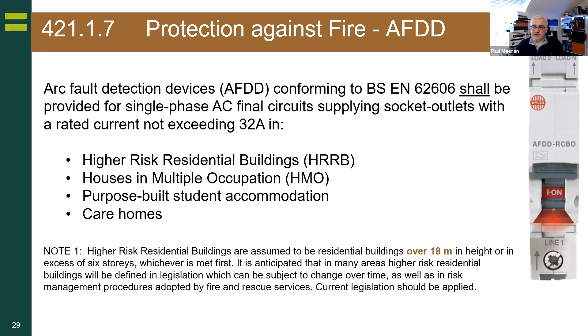For me, I'd use the rule of thumb: anything a plumber can touch. Immersion heaters are high current using technology, and there's a reason behind that which we'll get onto. But for all other premises, the use of AFDDs is recommended up to 32 amps.